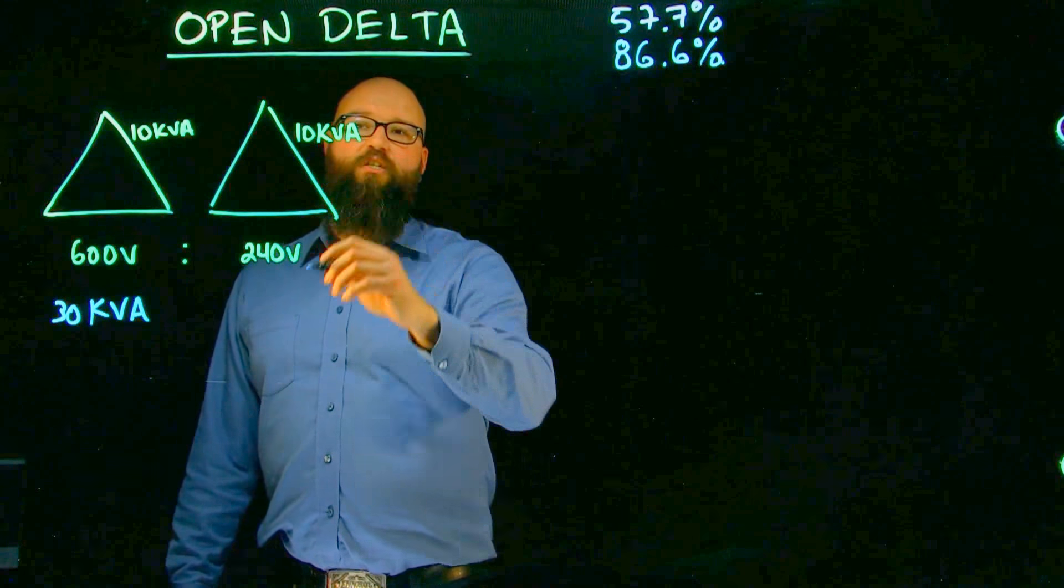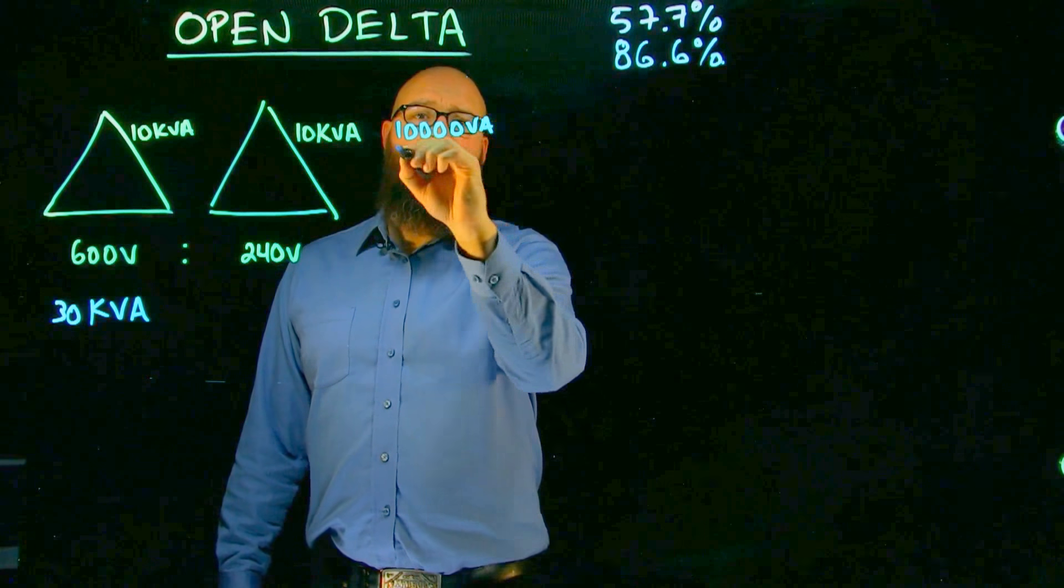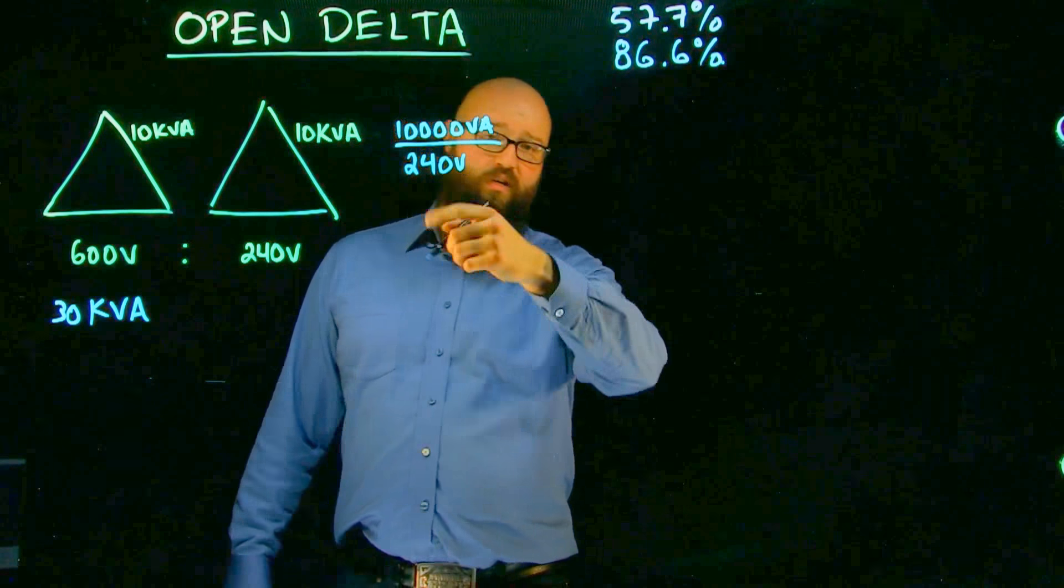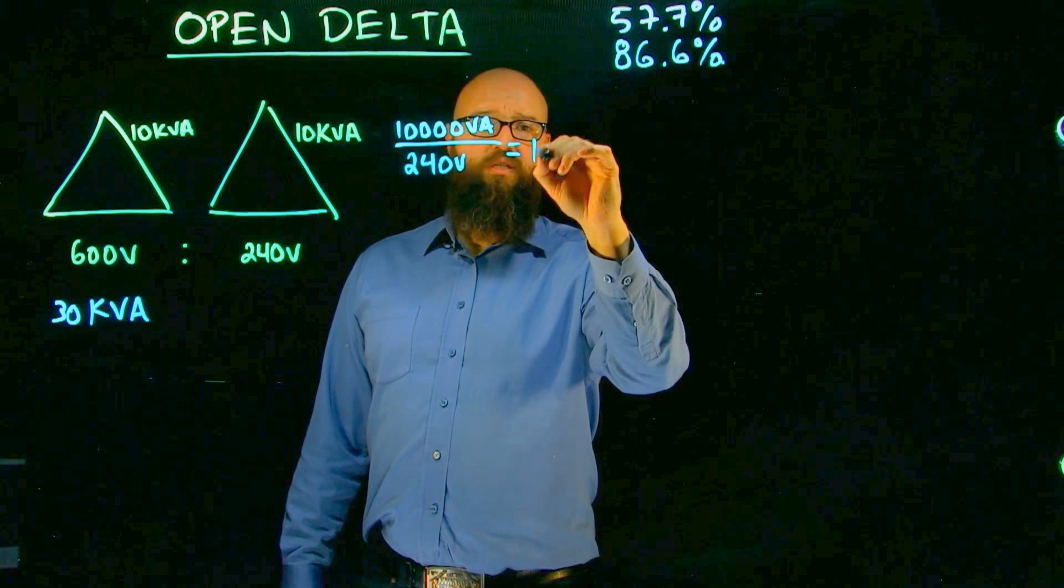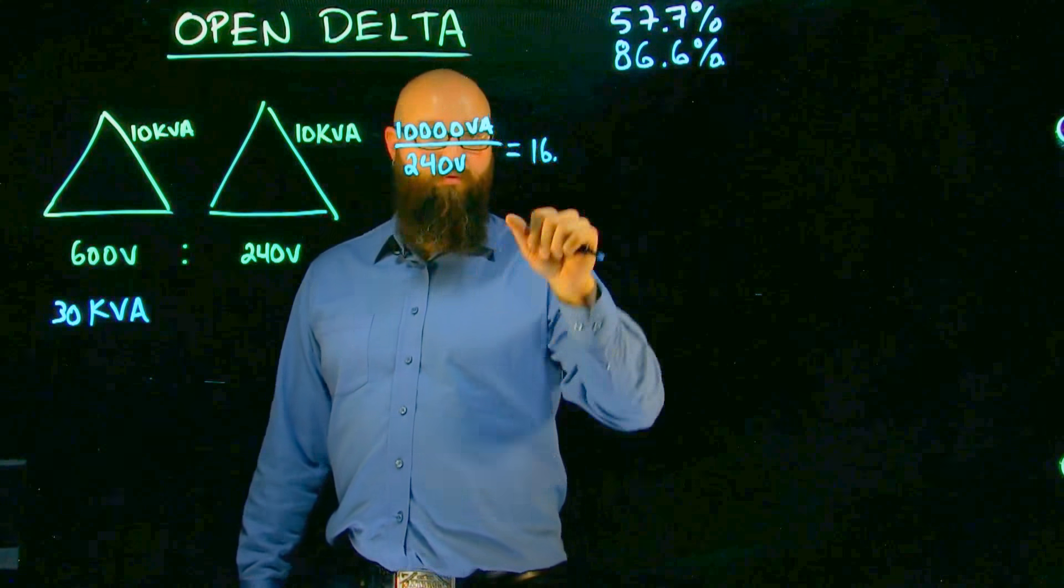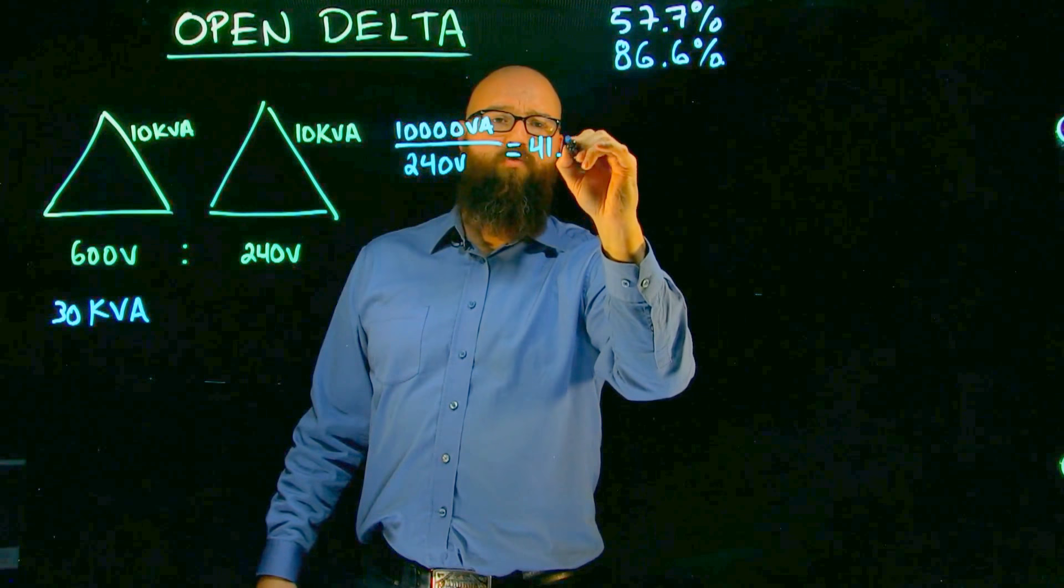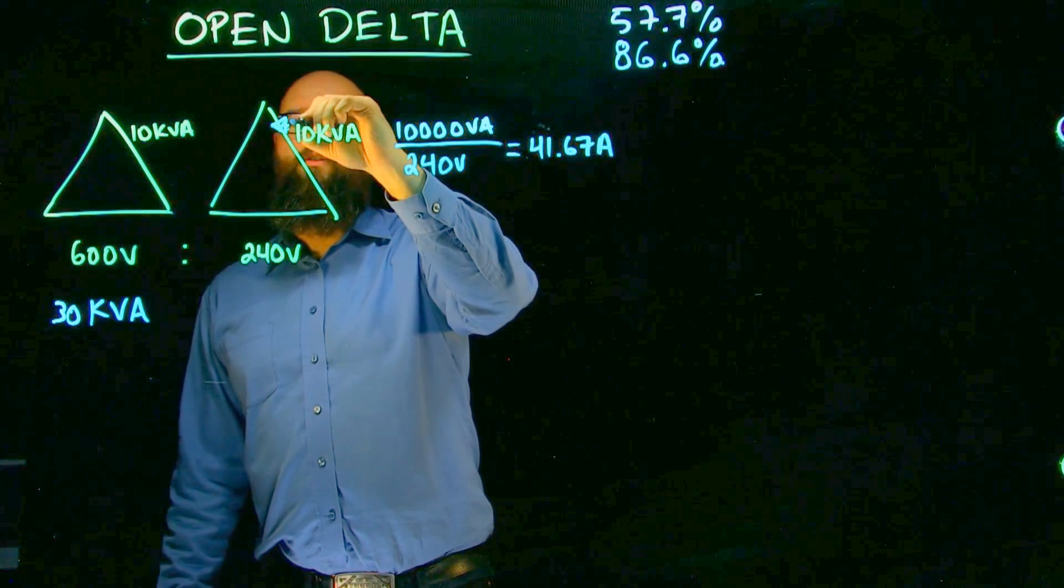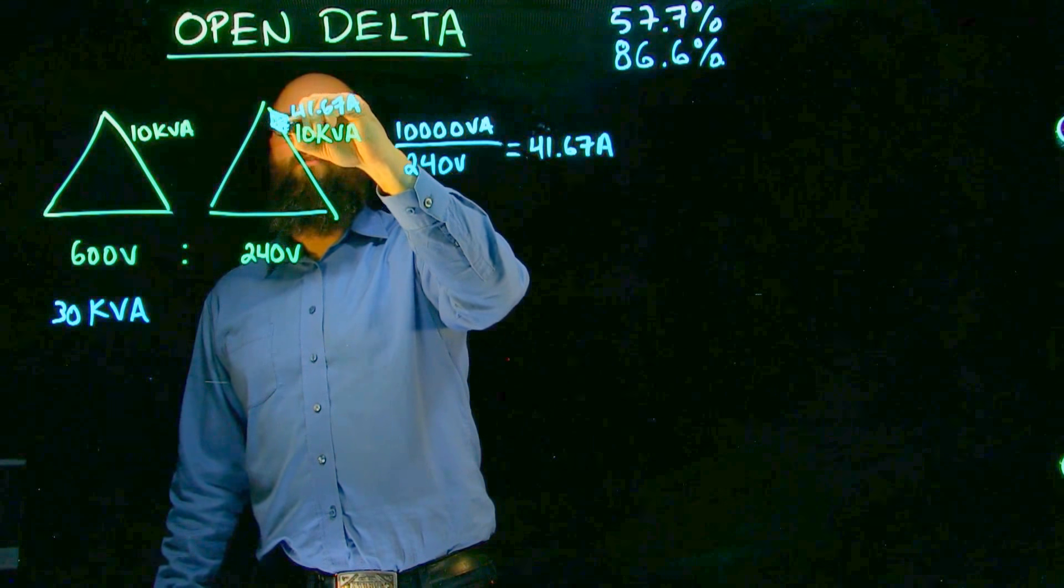So if we look at each individual phase, we have 10,000 VA divided by our phase voltage of 240 volts which gives us, we should see 16, no that's our primary. We don't worry about our primary right now. We're going to look at about 41.67 amps phase current. There's 41.67 amps. Let's draw that going the other way.